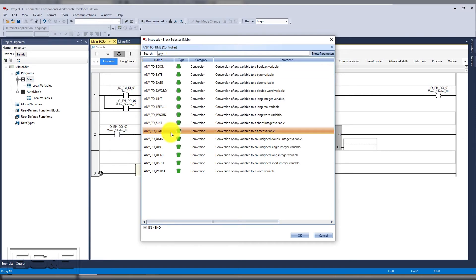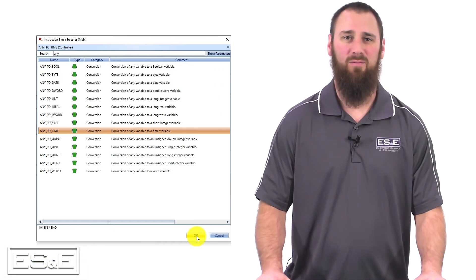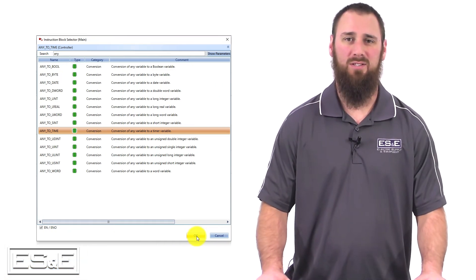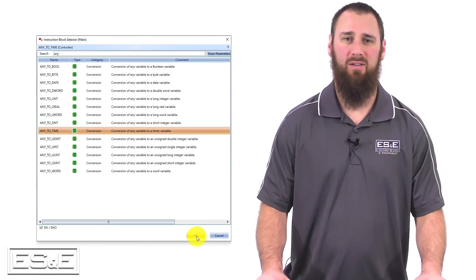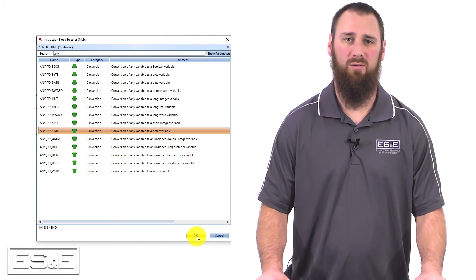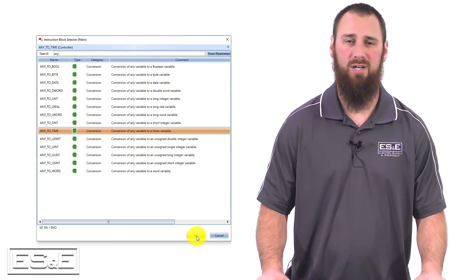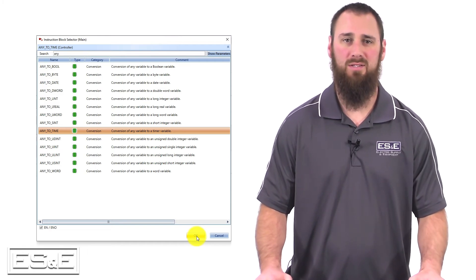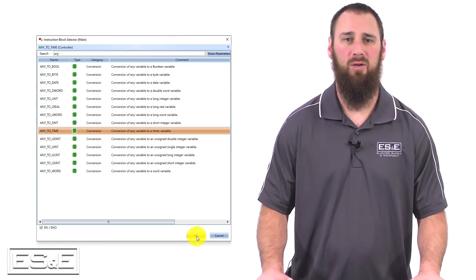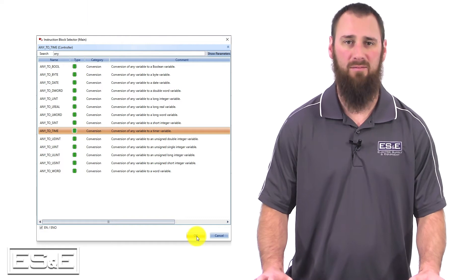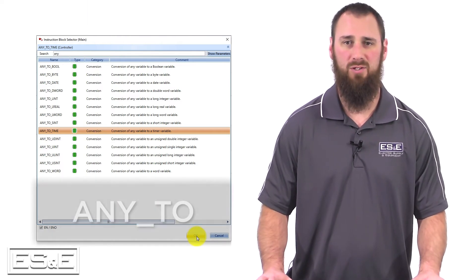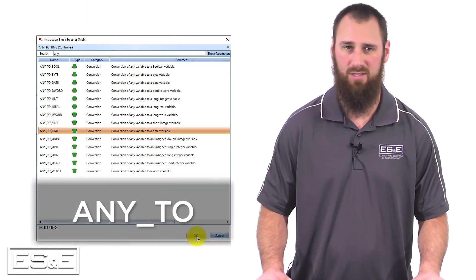Then you can use the search for any to time and this allows us to take a tag value and convert it into the time data type, which is required for PT and ET. In Logix software, the instructions automatically convert the data format to the required output type of that instruction. But in CCW, we do not have that, so that is why the conversion instructions exist.